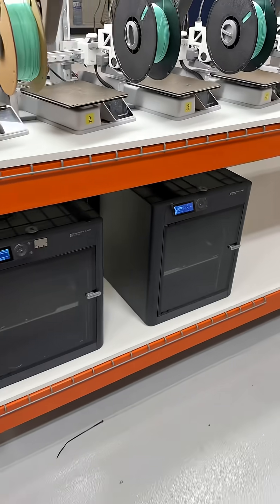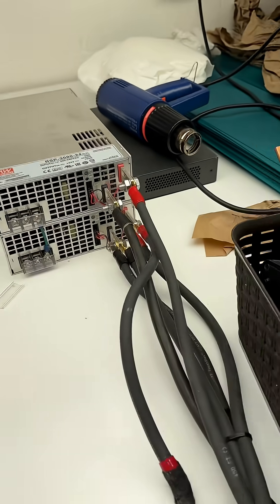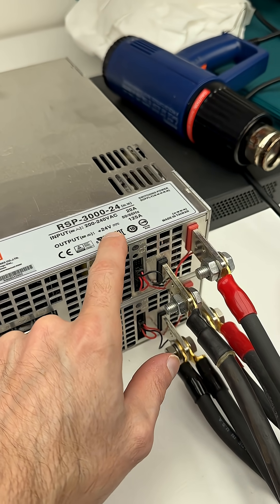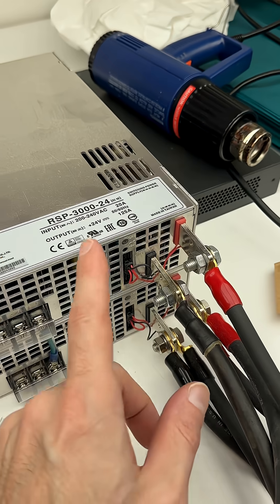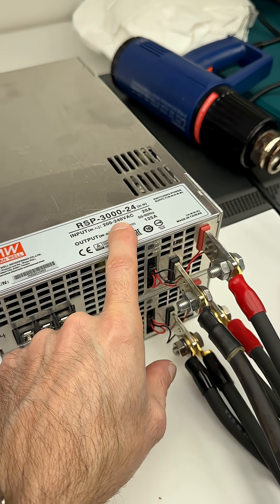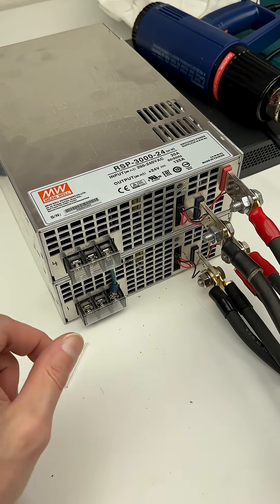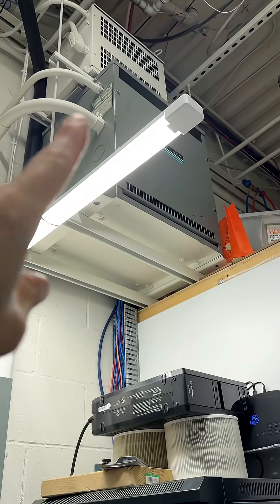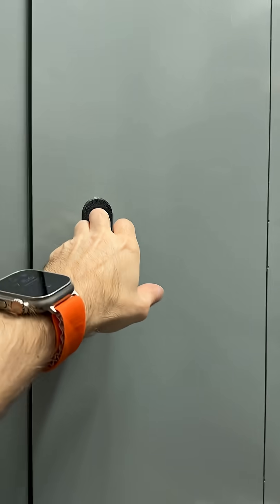Now I know there are going to be two questions about why I'm doing this. Our old printers ran on these large Mean Well power supplies — they output 24 volts, 125 amps a piece, and we had six of these running the old print farm. These are 3,000 watts a piece, and because we had three-phase power here we were running these on 208 with a 12 gauge wire feeding them. That's all supplied by this big transformer and everything is already set up inside this panel.